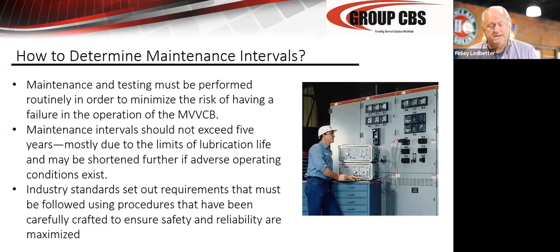Now, there's as many opinions on this as there are stars in the sky. Basically, what you have to think about are these critical circuits. And if they're critical circuits, then you have to take a more critical approach to your maintenance cycle. If they are not critical circuits, you might take a different approach. And in certain industries, the run-to-fail model is certainly attractive because you essentially mount a SWAT team every time you have a fire and put it back in service. And that's a common approach in a lot of industries.